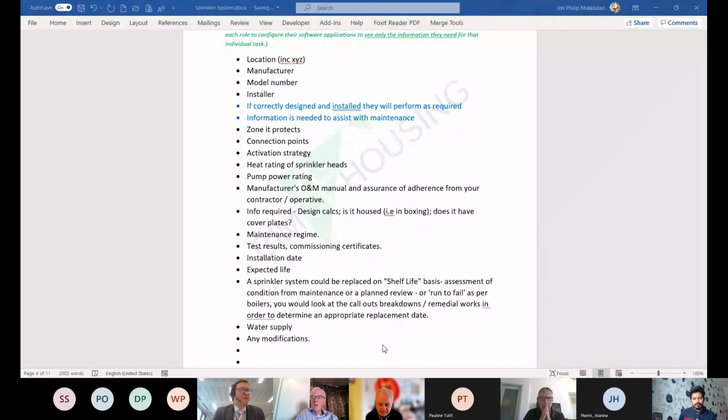Okay. Anybody got anything else to add? I'd just like to ask a question of Paul. You said galvanized pipe. Is that the pipe that's an integral part of the sprinkler system? Yeah, we had some. Alan probably knows about this. We had some problems on a job a while ago with seam welded galvanized pipe.